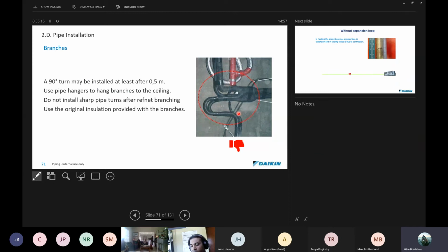We may not make U bends after RefNets, like this. This is detrimental because it transfers the force onto the Y joint in different directions and can cause these Y joints to start cracking. So any time a RefNet is returned to us and the guys tell us it's leaking, very often these things happen after a system has been running for a while. We will go to site and find that something has been done in the piping that caused the Y joint to crack. This will be from expansion and contraction, and also from illegal U joints and things like that that are not allowed in the system.